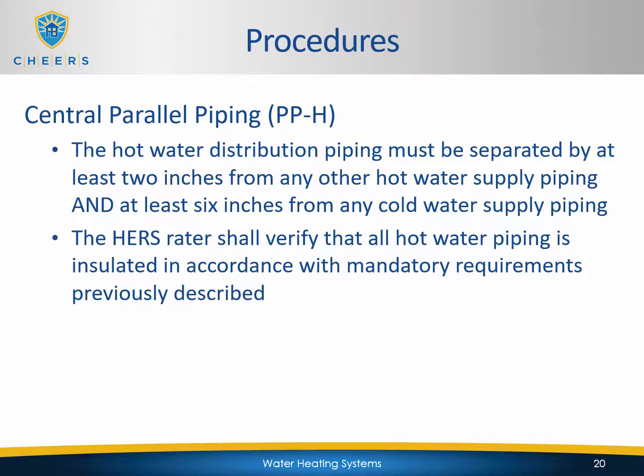The hot water distribution piping must be separated by at least 2 inches from any other hot water supply piping and at least 6 inches from any cold water supply piping. And this is to prevent any of that heat transfer either from a hot water line to another hot water line that may not be as hot, or from hot to cold, which would be even worse. So the HERS rater shall verify that all hot water piping is insulated in accordance with the mandatory requirements previously described. And so you're going to look at that table that we looked at, but again, it's most likely going to be 1 inch or R7.7.